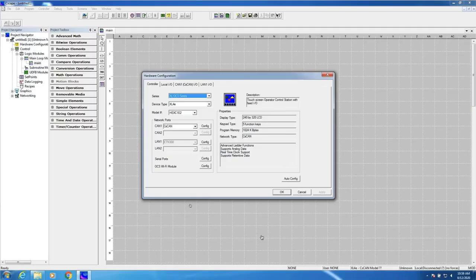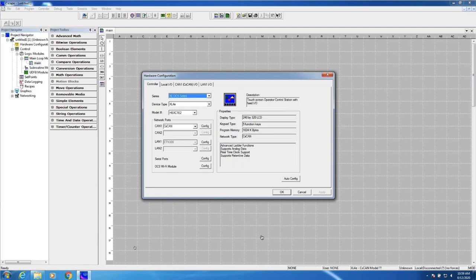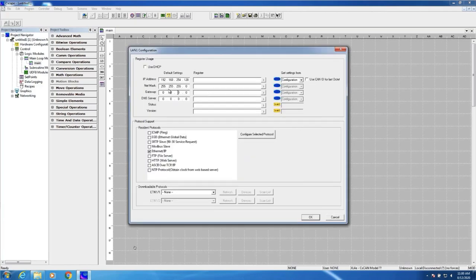Let's go ahead and demonstrate how to enable Ethernet IP as an I/O device for a typical Horner controller. In this case I'm looking at an XL4, one of our more popular controllers. We start in the hardware configuration and go under LAN 1 config. I need to configure at least a minimal amount of Ethernet functionality for Ethernet IP to work. In a real application I would assign tags or variables to IP address, net mask, et cetera — all those things could be changeable from the application touch screen. For now I'll leave it at the basic default Ethernet configuration.